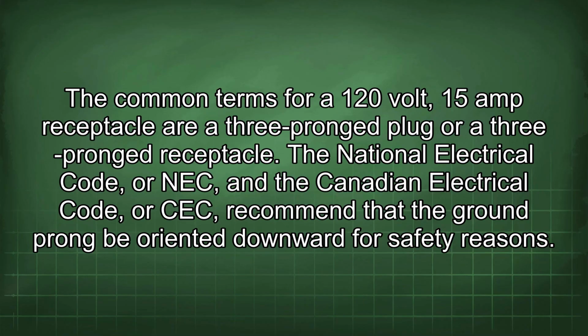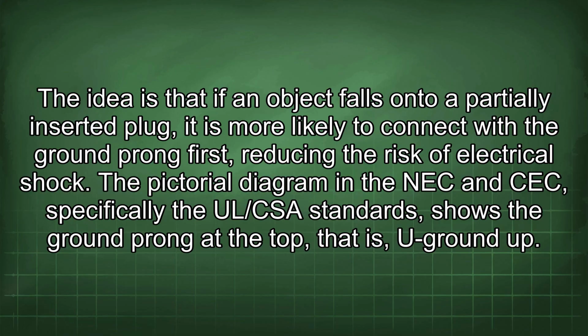Common terms for a 120-volt, 15-amp receptacle are a three-pronged plug or a three-pronged receptacle. The National Electrical Code, or NEC, and the Canadian Electrical Code, or CEC, recommend that the ground prong be oriented downward for safety reasons. The idea is that if an object falls onto a partially inserted plug, it is more likely to connect with the ground prong first, reducing the risk of electrical shock.